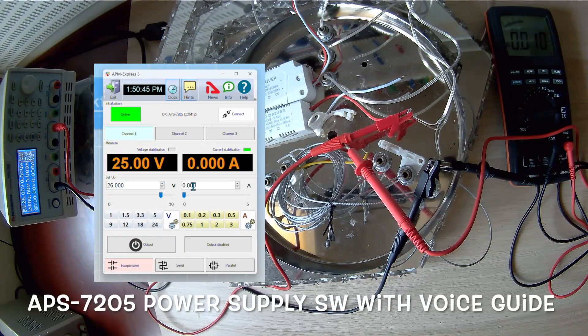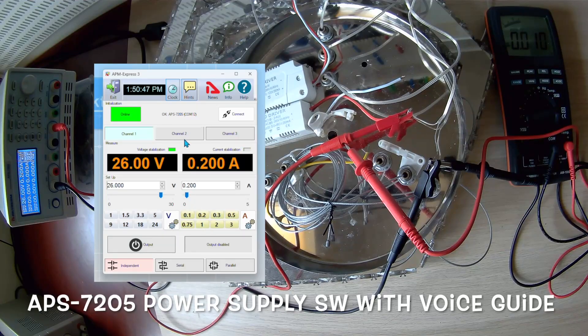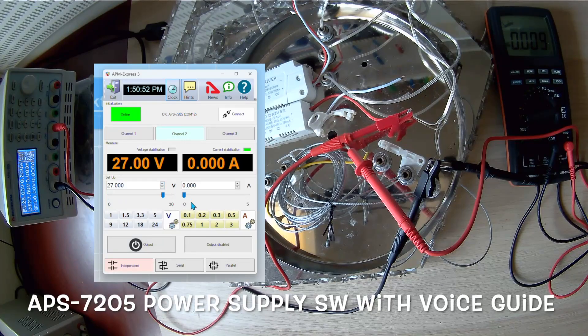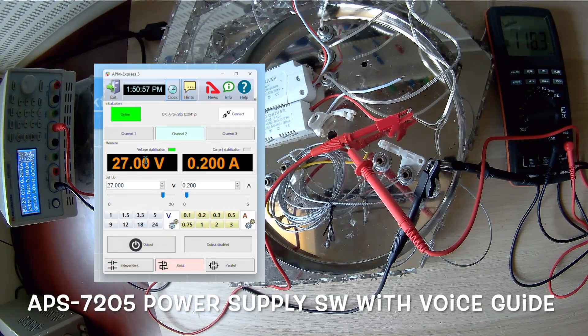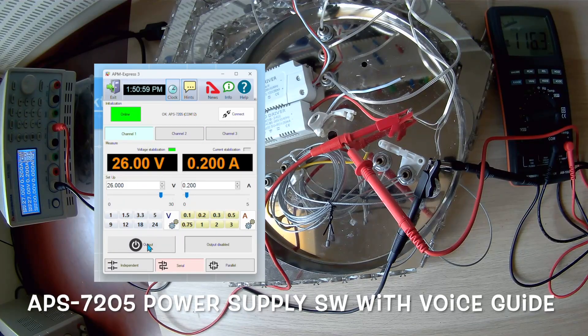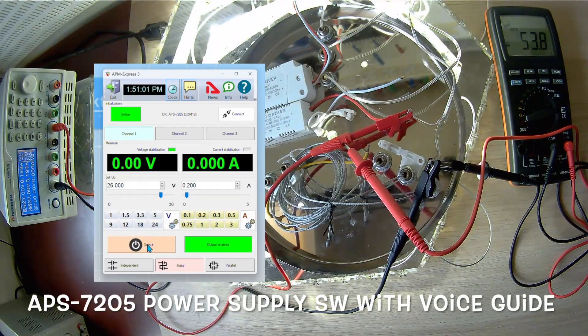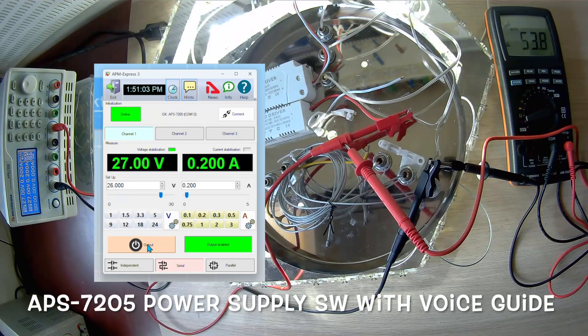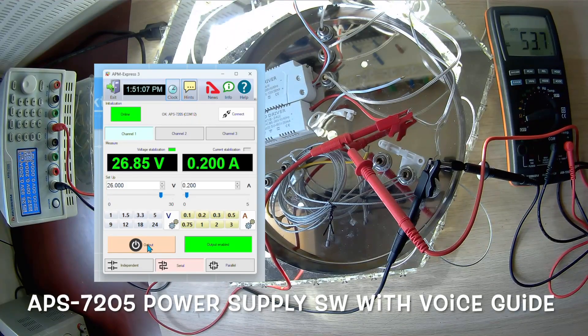To make our testing easier, we enable the remote control program via USB. We set 26V on one channel and 27V on the other and connect them in series. Total 53V. The total current is set at 200mA and now we turn on the APS7205 output.